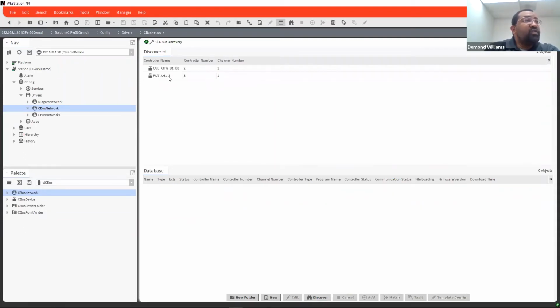So right now I have 2 controllers that are attached to my demo system here. One of the things I want to make sure everybody understands is that when you initially do your discover, of the controllers out there, whether it's an XL50, XL100, a Honeywell Zone Manager, or the XL500 controller or XL800 controller, it will pick those controllers up as one device. But some of those controllers could have multiple air handling units or fan coil units. If you're using a zone manager, now you're looking at VAV controllers. So as you pull those devices in, they do come in as one device. So you have to pay attention to how many devices are actually on each one of those controllers, because you're going to have to take into account how many points you need in your system as well.